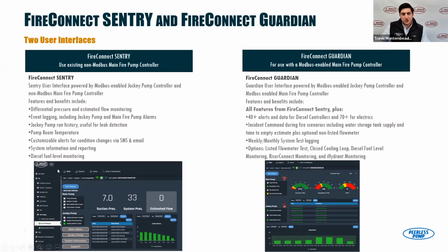We talk about this Sentry setup here. We call it Sentry when you don't have a Modbus enabled main fire pump controller. So we still have some smart fire protection monitoring, but we don't have everything. With those four dry alarm contacts, we can pick up other pump and other controller manufacturers as well. But when we're using the Modbus connection, we work with those four main, the heavies, if you will, in the industry. And that's a good segue into the difference between Sentry and Guardian.